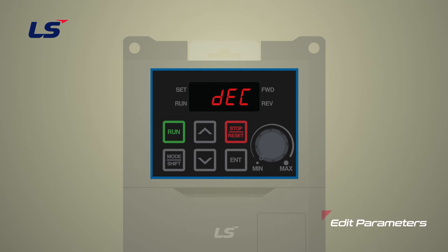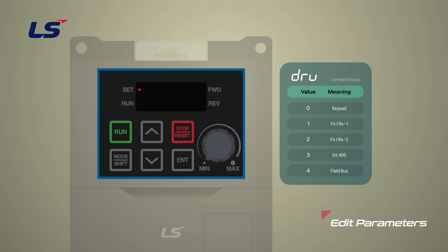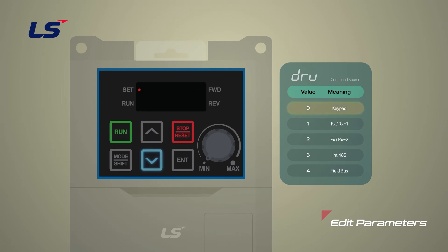Next, let's select the drive command source. Use the up and down arrow keys to move to the drive parameter. From here, press the enter key to enter the edit screen. When entering the edit screen, the previously set value blinks. Here, the meaning of numbers are shown in the table on the screen. If it is 1, it is set to FXRX1, which means the operation signal input through the multifunction digital input. In this example, we will change to 0 to operate with the keypad. Likewise, press the enter key twice to save the edited content.